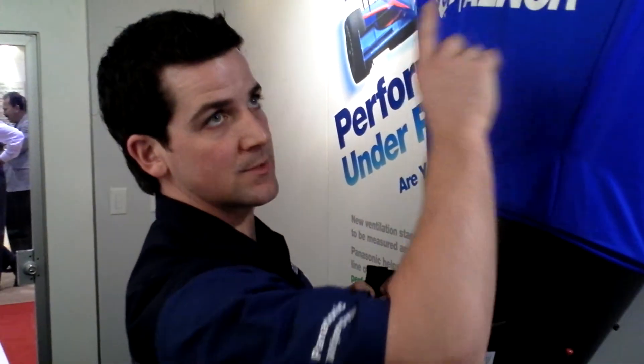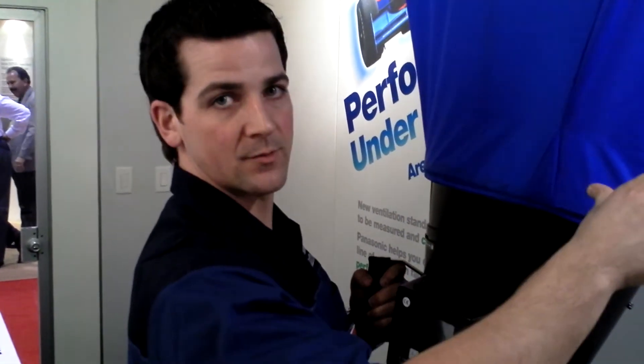By using this balometer, it's going to test the CFM. What we're running these fans at, every last one of them, is 0.25 static pressure. What that is, is pretty much an average install, whether it has a longer duct run, or if it has elbows, etc.